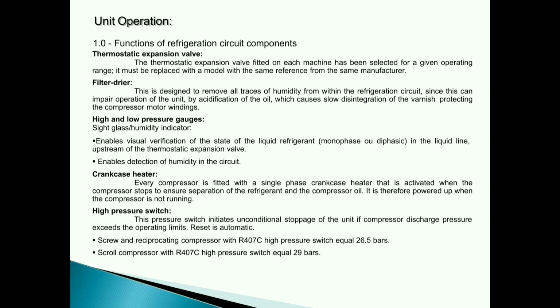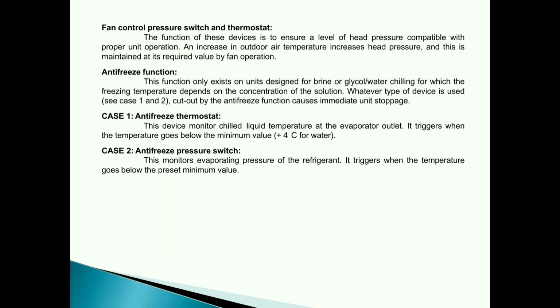High pressure switch. This pressure switch initiates unconditional stoppage of the unit if compressor discharge pressure exceeds the operating limits. Reset is automatic. Screw and reciprocating compressor with R407C high pressure switch equal 26.5 bars. Scroll compressor with R407C high pressure switch equal 29 bars. Fan control pressure switch and thermostat. The function of these devices is to ensure a level of head pressure compatible with proper unit operation. An increase in outdoor air temperature increases head pressure, and this is maintained at its required value by fan operation.